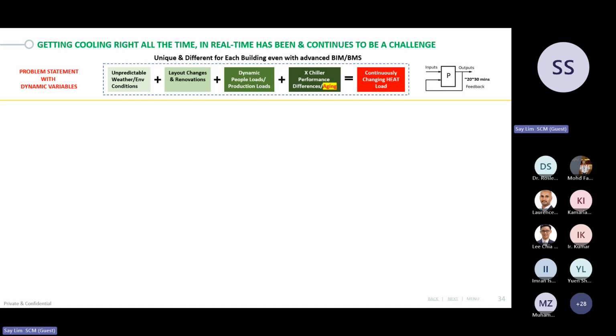Dynamic people load and production load change because of consumption and process cooling requirements, as does chiller performance, especially with aging. Like any equipment, performance deteriorates if not maintained well, and there can be spikes in requirements due to motor or other issues. So you have continuously changing heat load or air requirements, and because of this, there's always a design factor of about 25% more capacity.